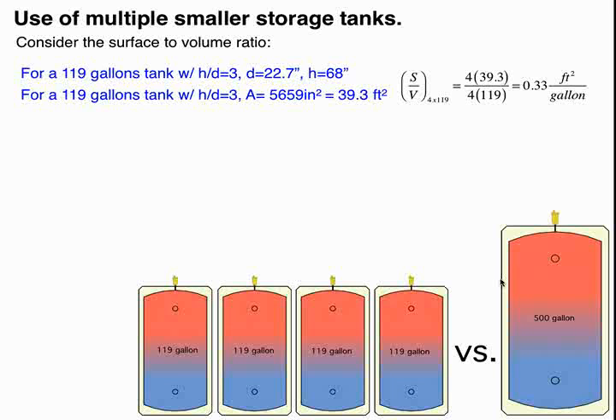Anything that reduces the surface to volume ratio is beneficial. And if you think back to some of your geometry, you probably remember what's the 3-dimensional shape that has the lowest surface to volume ratio? And the answer is a sphere, or a ball, has the lowest surface to volume ratio. And very rarely you will see a spherical tank. They're used with cryogenic fluids because you have such an extreme delta T there that it's worth the cost to fabricate a spherical storage vessel to minimize heat loss. But spherical storage vessels are just not cost effective for HVAC applications.